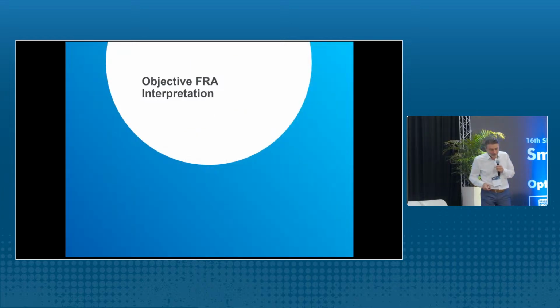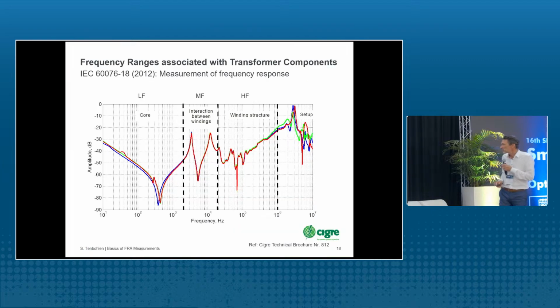And so we had a working group which analyzed different interpretation schemes. Very shortly, we have here the measured frequency responses of one transformer. We have here the frequency range from 10 hertz to 1 megahertz. And you can see here in the lower frequencies, the core is responsible for the response. Here in the middle frequency, it's interactions between windings. In the high frequency range, it's winding structure. And above 1 megahertz, it is more or less the measuring setup which has an influence.